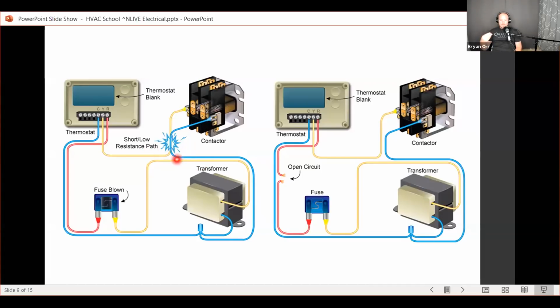It can be an undesigned low resistance path in between switch legs. This is disputed territory, but I just use the common terms in our industry. A good example would be a short between this yellow wire coming from my thermostat, which is the control circuit that powers my contactor, and, this is a very simple one, imagine that this yellow wire was shorted to the white wire. What would happen? It would also energize whatever the white wire was hooked to. That could be the furnace, or electric heat strips in the case of a heat pump. And so we would call that a short.